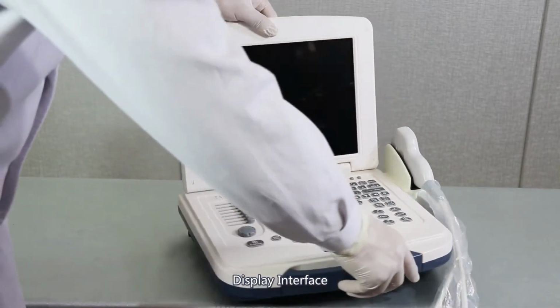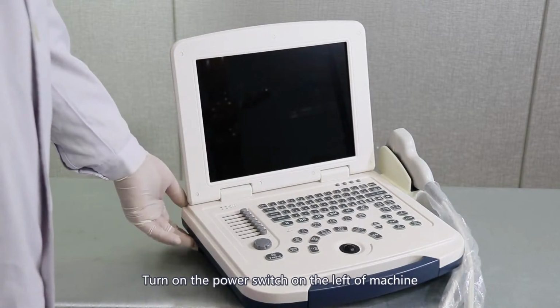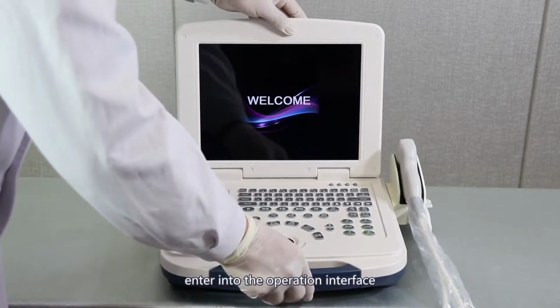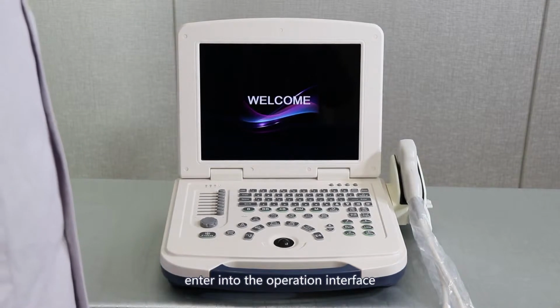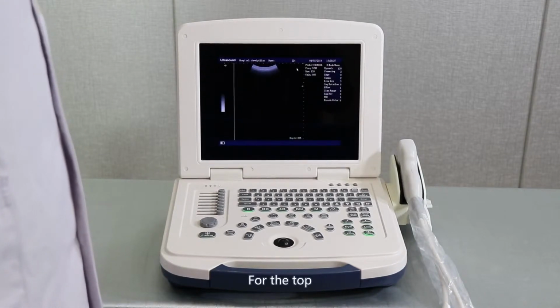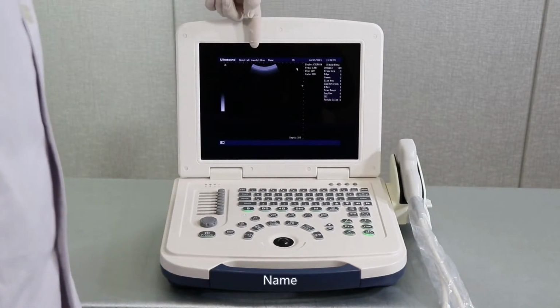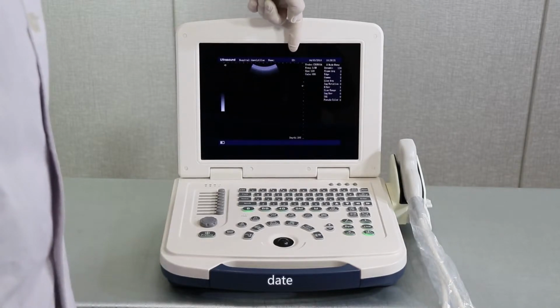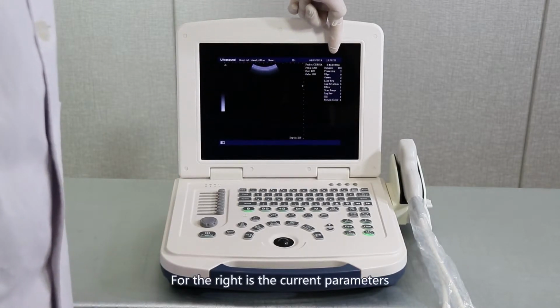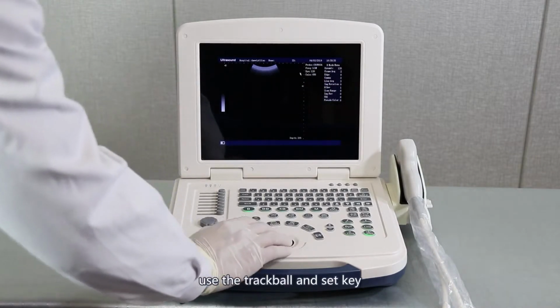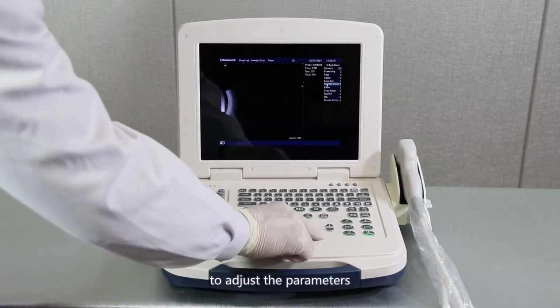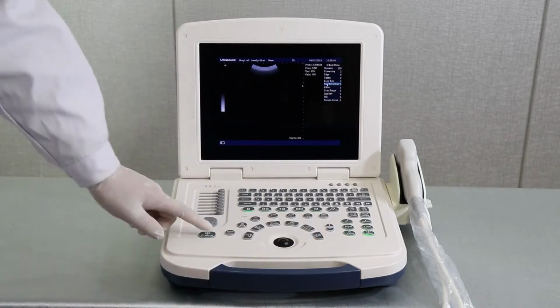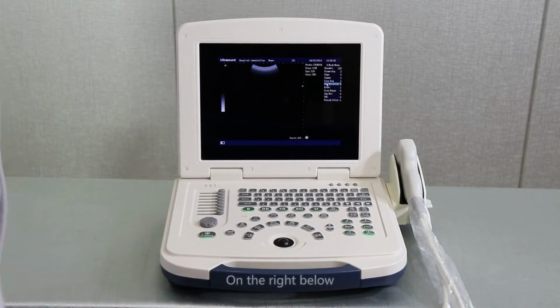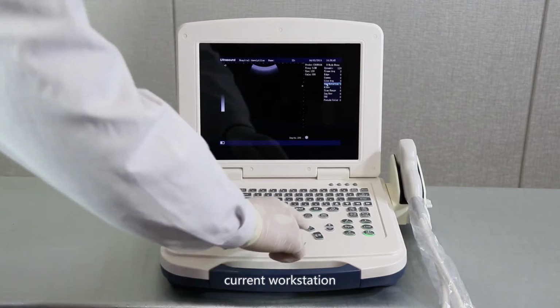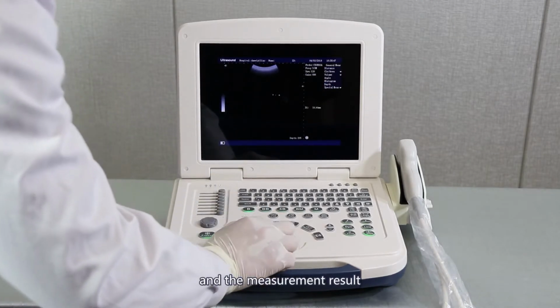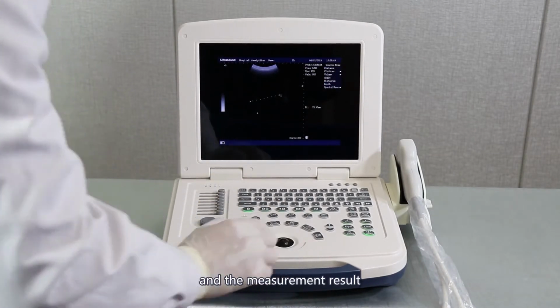Display interface. Turn on the power switch on the left of the machine. Enter into the operating interface. For the top is the hospital, name, ID, date, and time. For the right is the current parameters. Use the trackball and set key to adjust the parameters. For the right below is the DIPS, current workstation, and the measurement result.